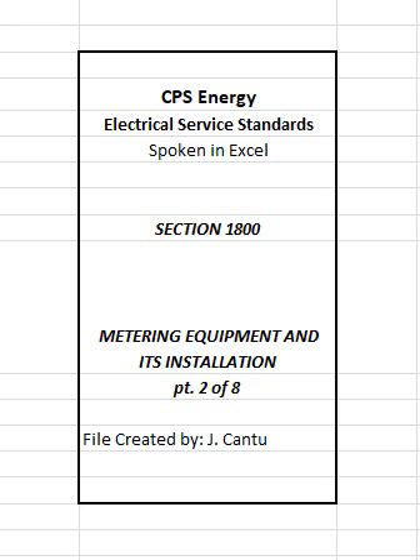Enclosure may be mounted on a meter pole with a meter rack, refer to Figure 1402, or directly on the building or structure, refer to Figures 1811 and 1813. C. For overhead to underground service, the CT/VTs will be installed by customer within an enclosure furnished by CPS Energy. Enclosure may be located on a metering equipment rack or directly on the building or structure. Refer to figures 701, 1813, and 1820.